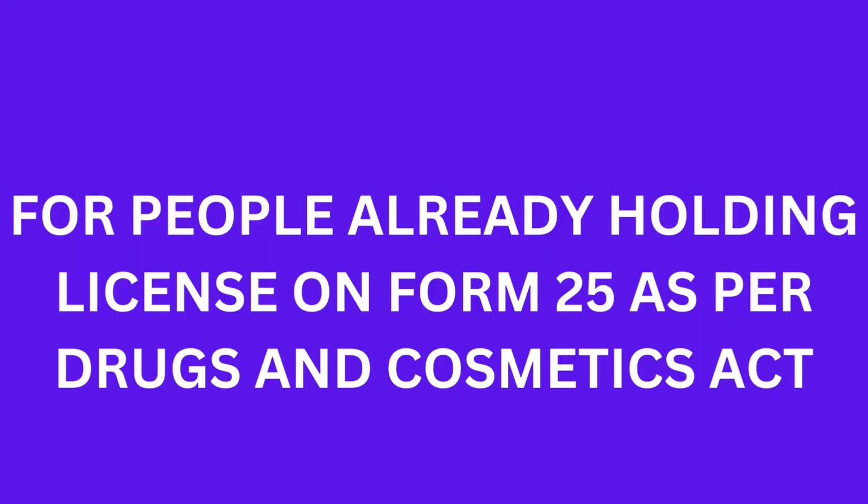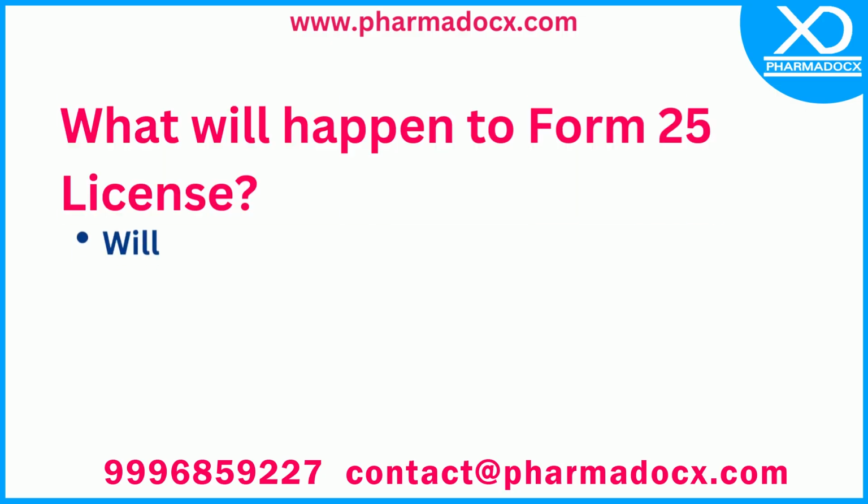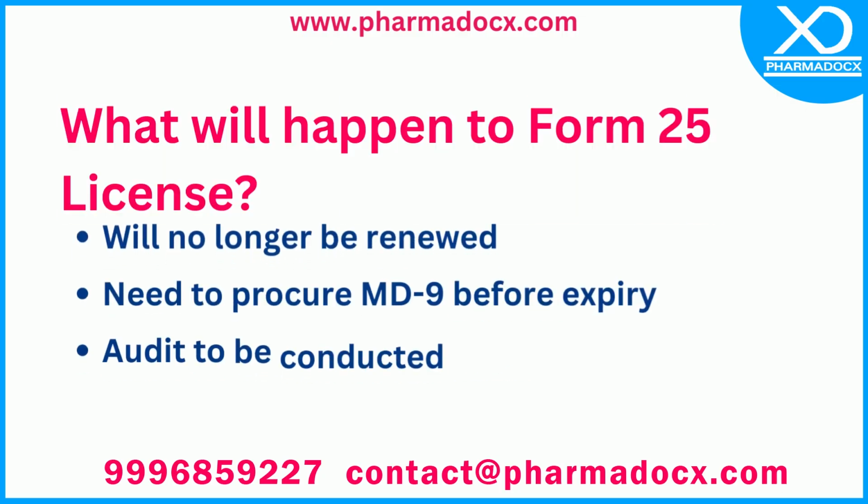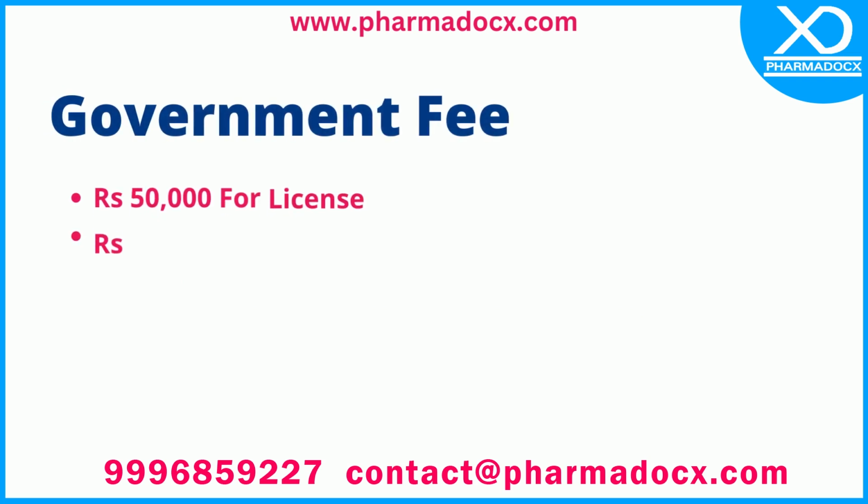Now we will discuss about people already holding license to manufacture hemodialysis solution on Form 25 as per Drugs and Cosmetics Act. The license on Form 25 will no longer be renewed. The manufacturer has to obtain the license on Form MD9 prior to expiry of the license granted on Form 25. Audit for grant of license on MD9 will be conducted again. Government fee for the license is Rs 50,000 for license and Rs 1,000 per product. The license is granted for a period of 5 years and can be renewed.